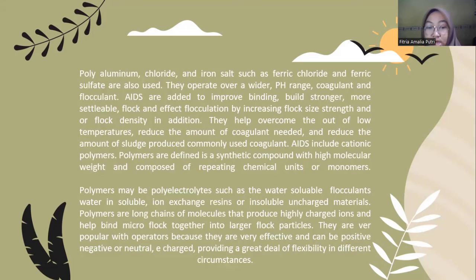Polymers are long chains of molecules that produce highly charged ions and help bind microfloc together into large floc particles. They are very popular with operators because they are very effective and can have a positive, negative, or neutral charge, providing a great deal of flexibility in different circumstances.